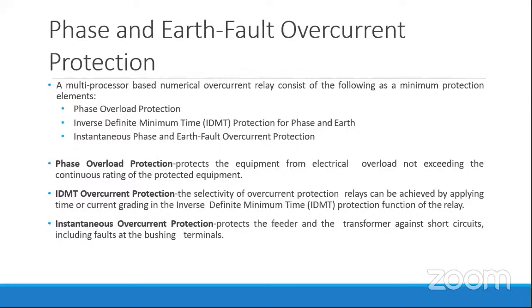Nowadays, numerical relays have all these features in a single compartment rather than using three units or different units for every separate protection. So the IDMT based protection, that is, the multiprocessor based numerical overcurrent relay, has the following protections as a minimum, as basic protection elements: phase overload protection, inverse definite minimum time protection, and instantaneous phase and earth fault protection.